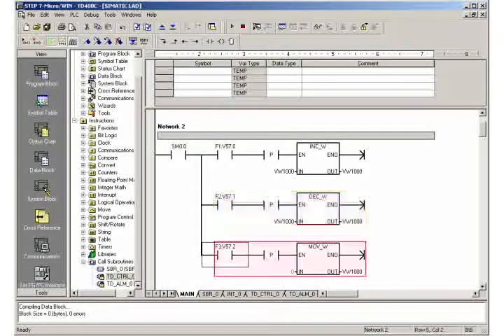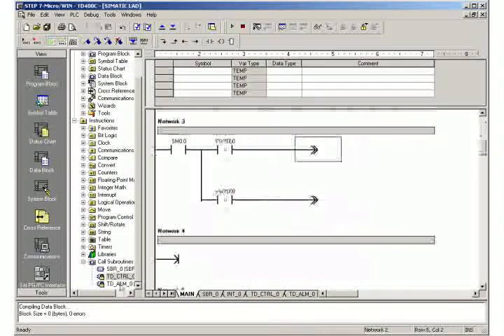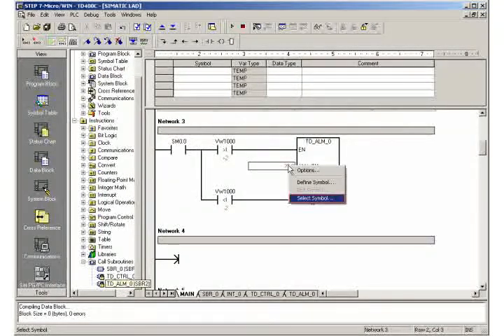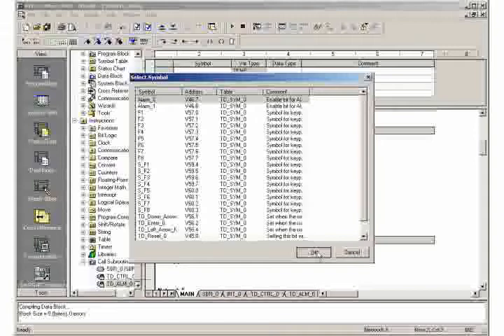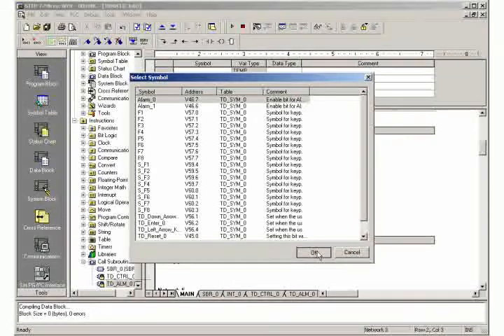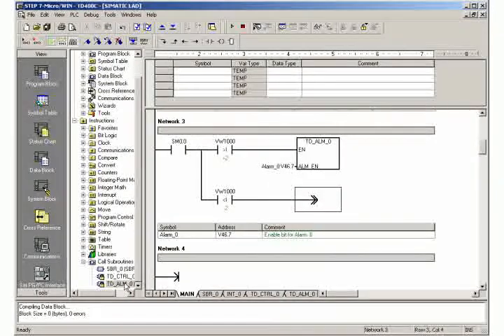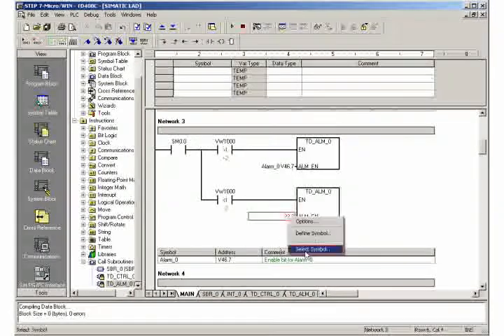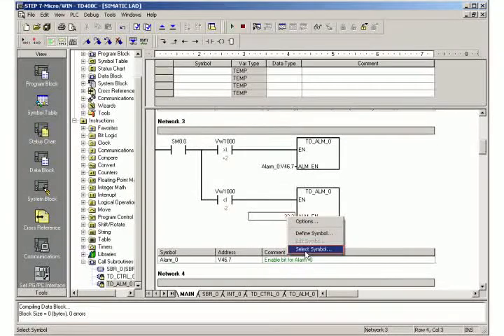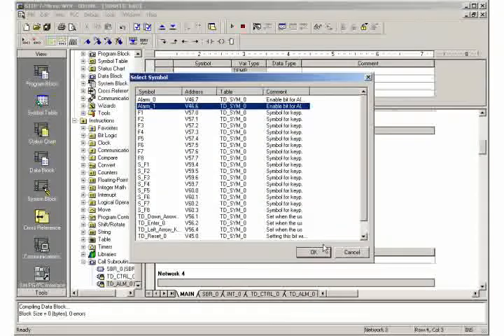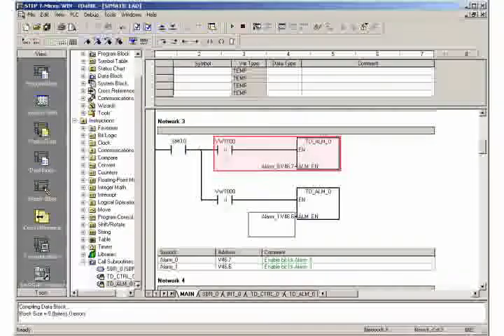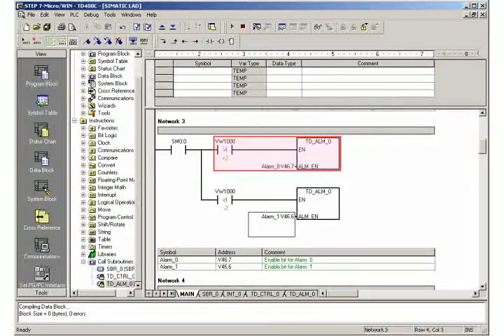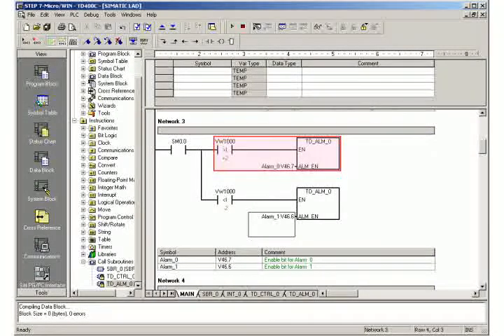Program the alarm calls in network 3. You find the corresponding alarm addresses by right-clicking and selecting the symbol. If the value of VW-1000 is greater than 2, alarm 0 will be activated. If it is less than minus 2, alarm 1 will be activated.